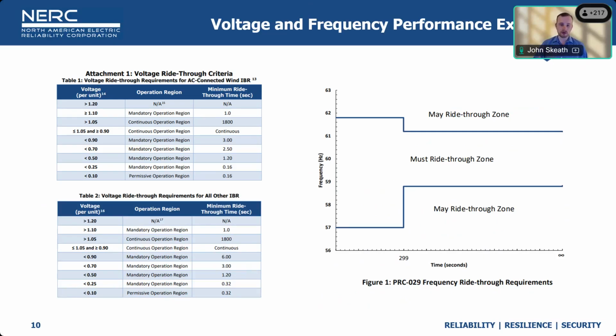The voltage is not graphed in a curve in the standard, but is in tabular form. So is the frequency, but we did draw the frequency in the standard attachment. So Table 1 is for those AC connected wind IBR voltage. Table 2 is then the voltage requirements for all other inverter-based resources. This is important as NERC's definition of inverter-based resource excludes Type 1 and Type 2 wind, but does include Type 3 and Type 4 wind plants.